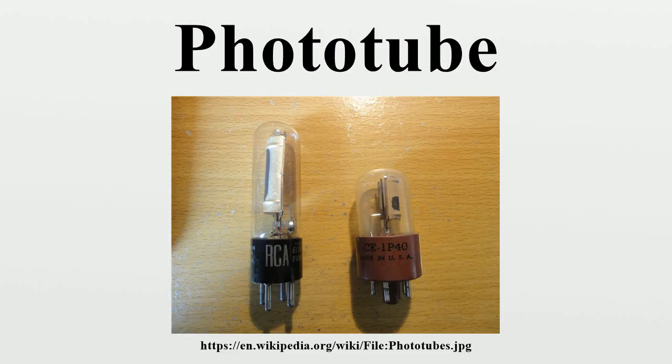The light wavelength range over which the device is sensitive depends on the material used for the photoemissive cathode. A cesium antimony cathode gives a device that is very sensitive in the violet to ultraviolet region, with sensitivity falling off to blindness to red light. Cesium monoxidized silver gives a cathode that is most sensitive to infrared to red light, falling off towards blue, where the sensitivity is low but not zero.